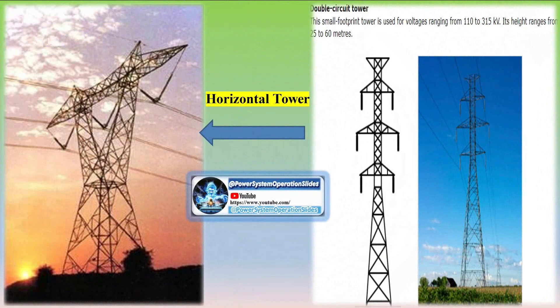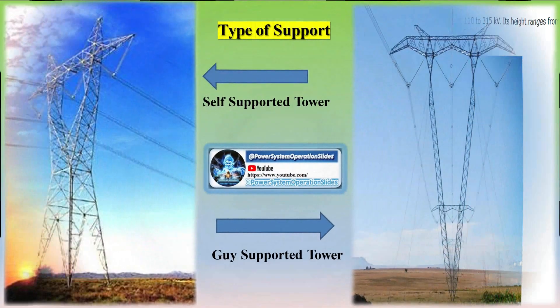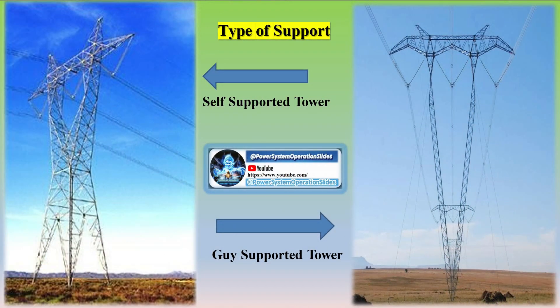The size and distribution of ice and snow loads depend upon the climate and local conditions. The wind force is usually assumed to be acting on a horizontal plane; however, depending on local conditions, a sloping direction may have to be considered. Also, different wind directions in the horizontal plane must be taken into account for the conductors as well as for the tower itself. The maximum wind velocity does not occur simultaneously along the entire span, so coefficients are introduced into load calculations to account for this.